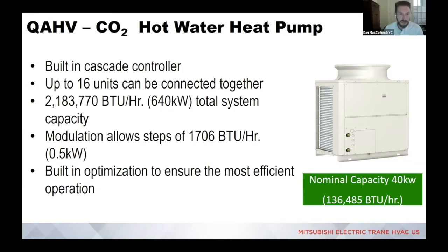So it is a self-contained system. Those two connections that you see at the unit right there in that image are water connections. They are not refrigerant connections. So all of the refrigerant is housed inside the unit. Like I said, we have had a system operating for quite some time in Norway down to the -30s, and we have not had freezing issues. The system does have a defrost cycle that it can activate as needed to shed any built up ice or condensation on the coil itself. So there's an internal circuit that's designed to prevent those types of issues, just like we do with the VRF heat pumps.